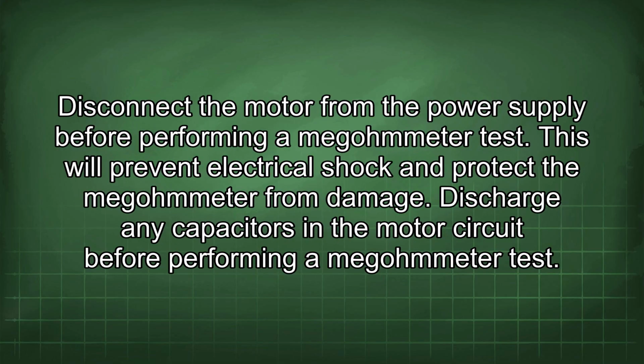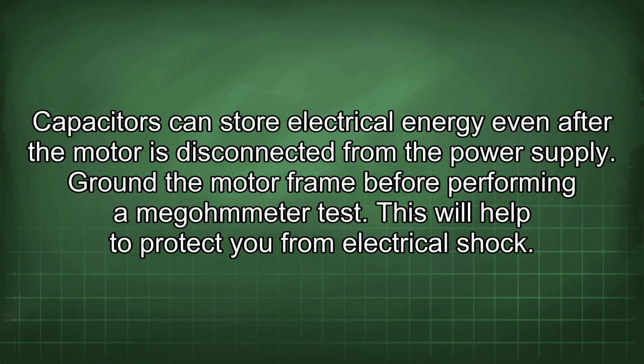Disconnect the motor from the power supply before performing a megohmmeter test. This will prevent electrical shock and protect the megohmmeter from damage. Discharge any capacitors in the motor circuit before performing a megohmmeter test. Capacitors can store electrical energy even after the motor is disconnected from the power supply. Ground the motor frame before performing a megohmmeter test. This will help to protect you from electrical shock.